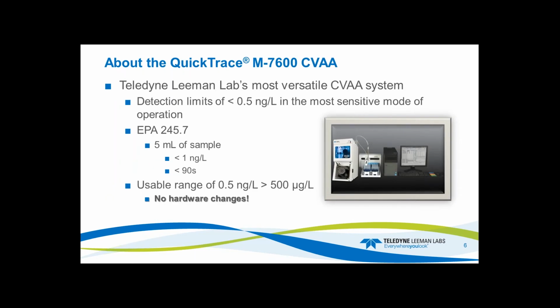The M7600, Teledyne Leeman Labs creates this system, and this is our most versatile cold vapor atomic absorption system. Detection limits of less than 0.5 nanograms per liter in the most sensitive mode. It's acceptable for EPA 245.7. It meets all the criteria. 5 mL of sample in less than 90 seconds will give you a method detection limit of 1 nanogram per liter.